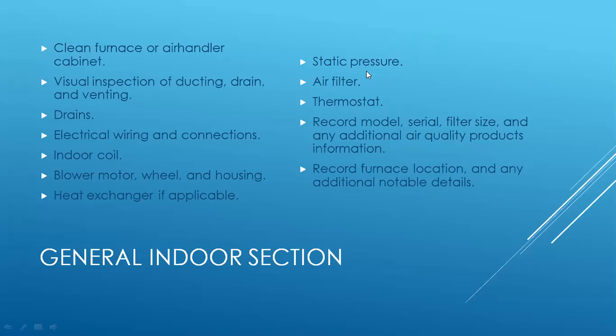I would recommend it because you can determine a lot of issues with the system. That may be something where they need additional ductwork later. Or it could be that they're using too restrictive of a filter. But you're kind of ruling out some things just by taking a 2-minute test. Always check the filter. If you replace the filters as part of the tune-up, by all means. If you don't, they want to purchase one, sell them one, or if it's their responsibility to replace it, note that on your invoice. So if it's not changed down the road, it's not a callback, it's a billable item.